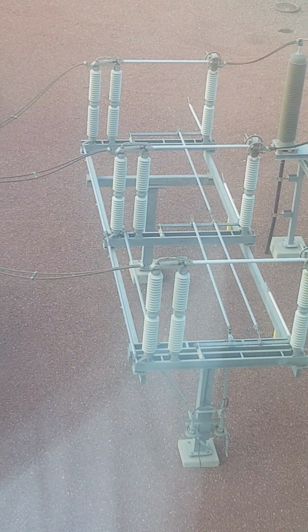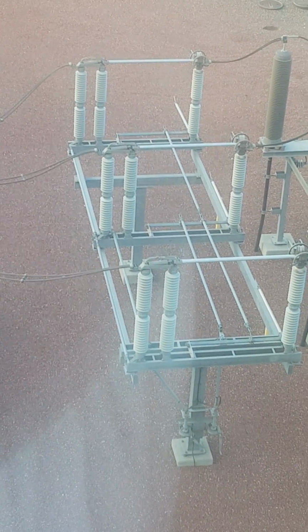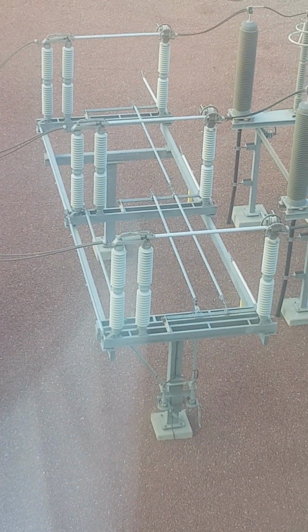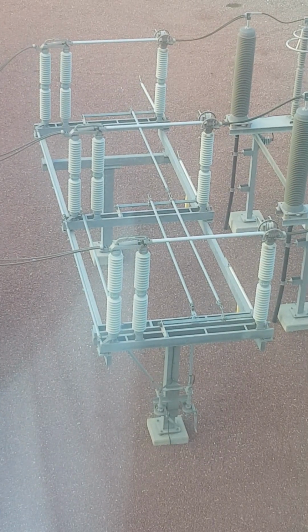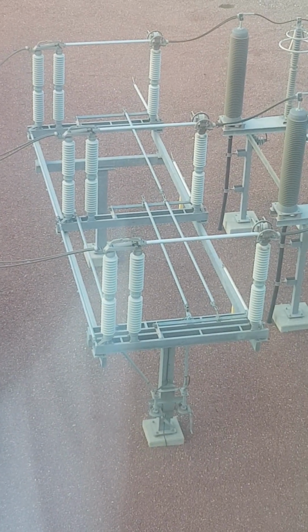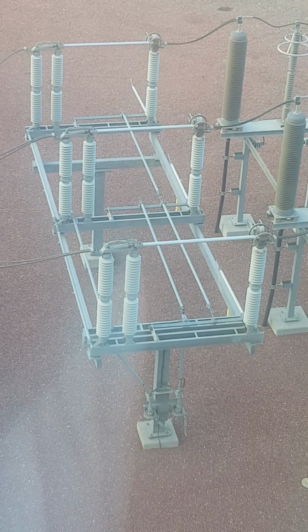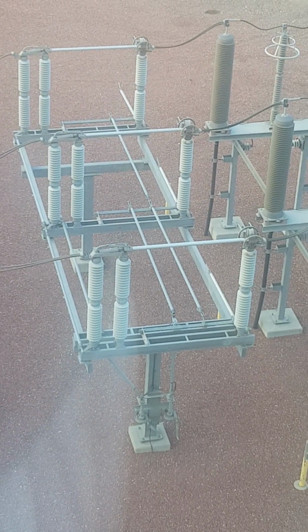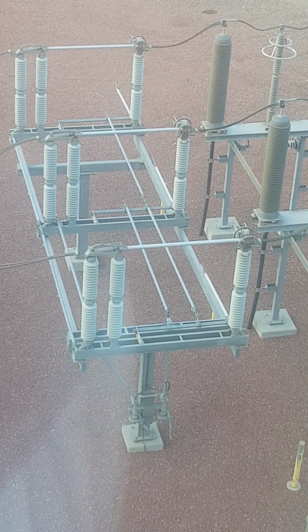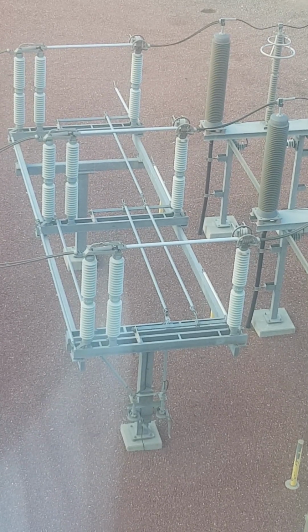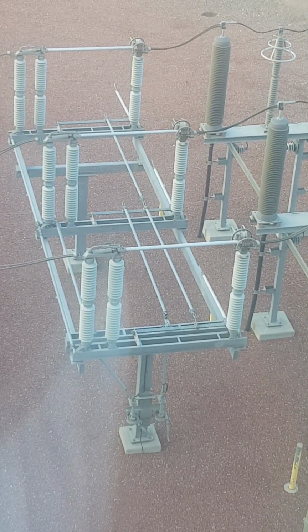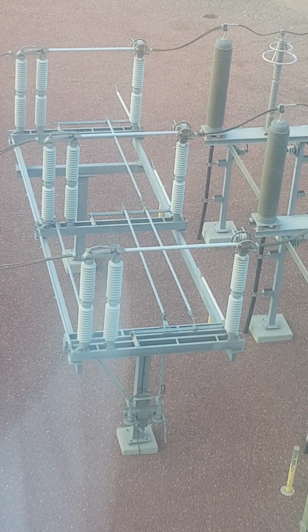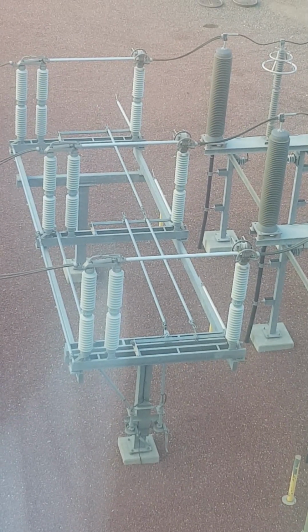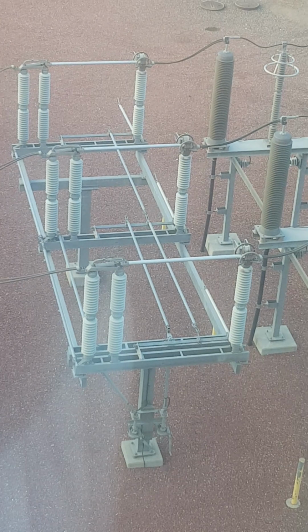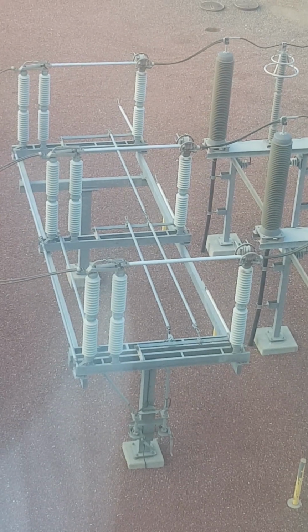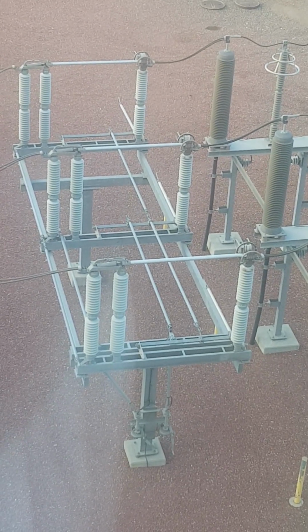What we'll see is a three-phase disconnector. Usually these disconnectors are open, just to open the circuit to interrupt the power, but usually we open them when there is no power coming to the substation, because if you open them under load conditions, there will be a lot of arcing inside. But sometimes we do open them when the system is energized, but they are not meant to do that. And also, they are not meant to interrupt the fault current.